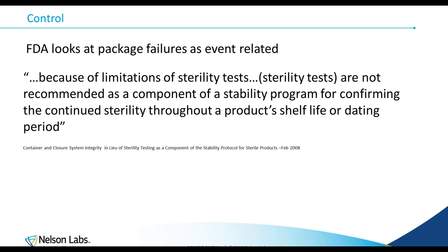So for control, FDA looks at package failures as event-related. We're going to talk about this later on, but we don't do sterility tests after accelerated aging and performance testing, but we do strength, integrity, and microbial tests.